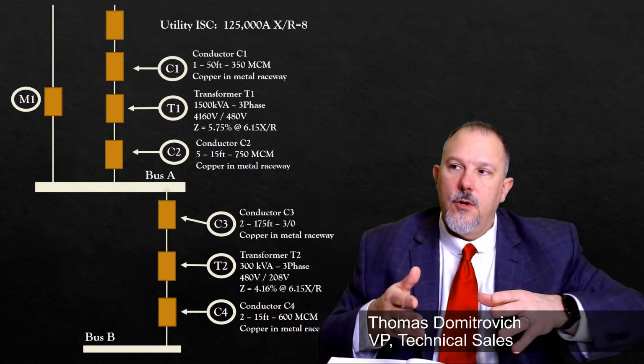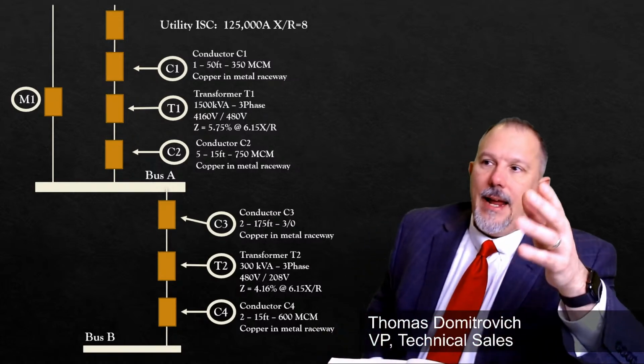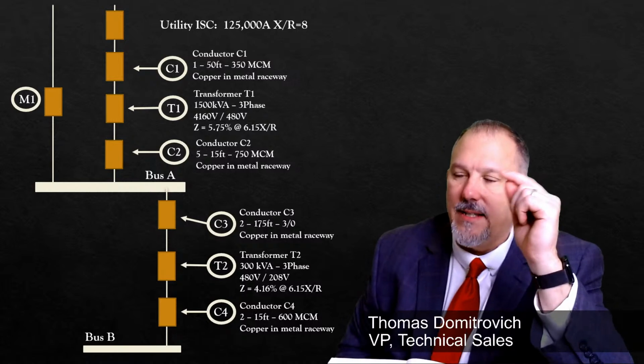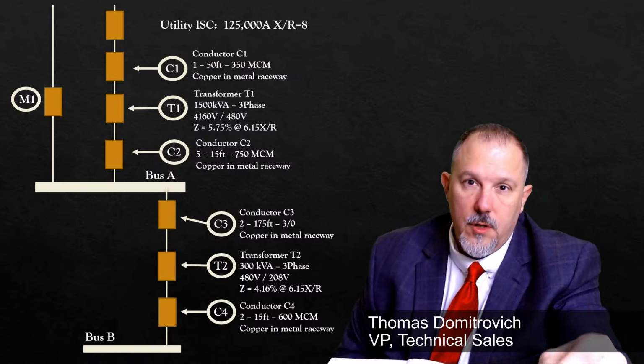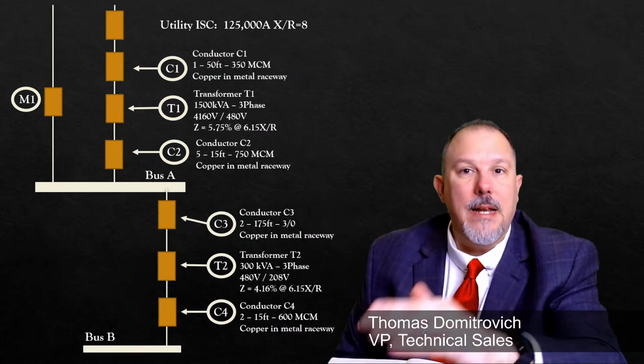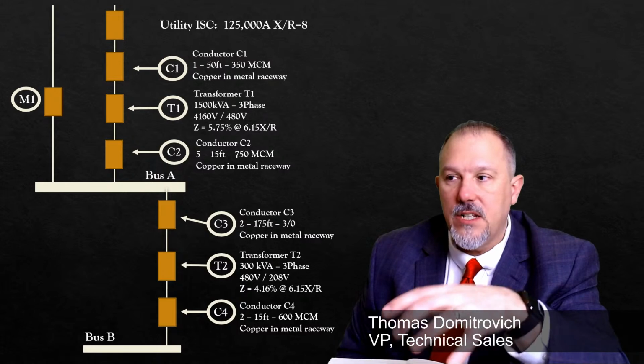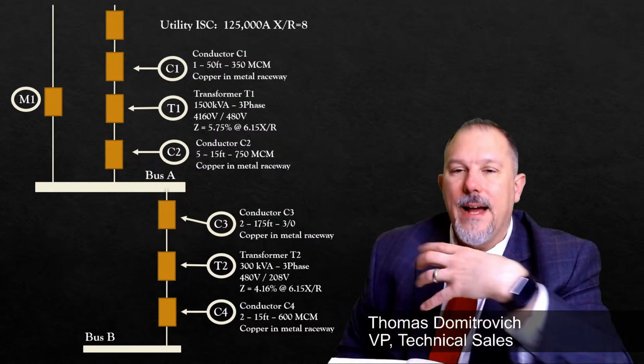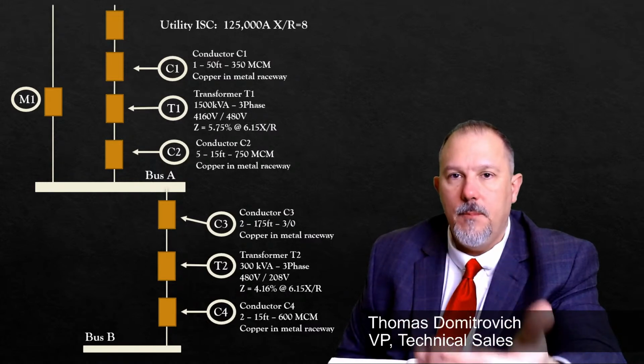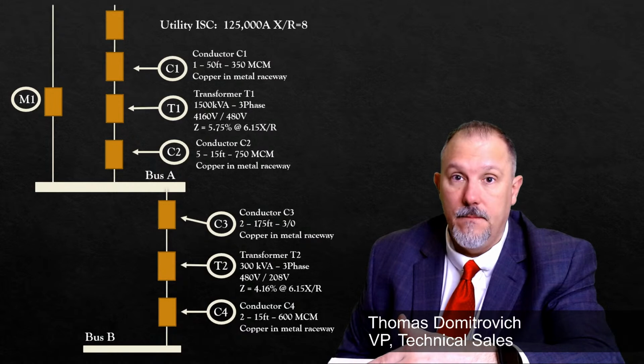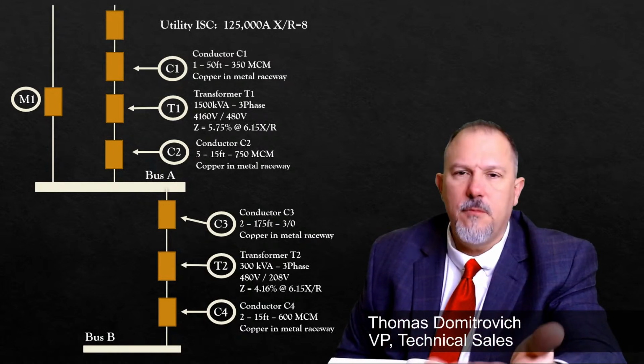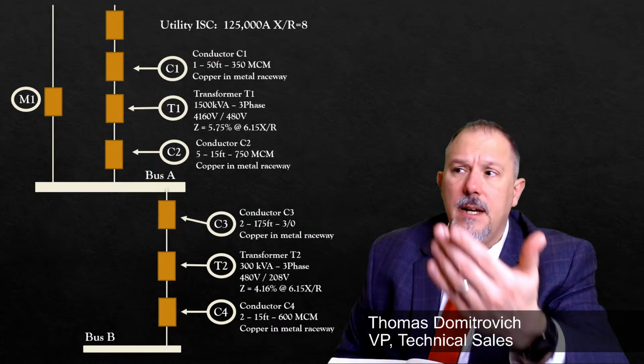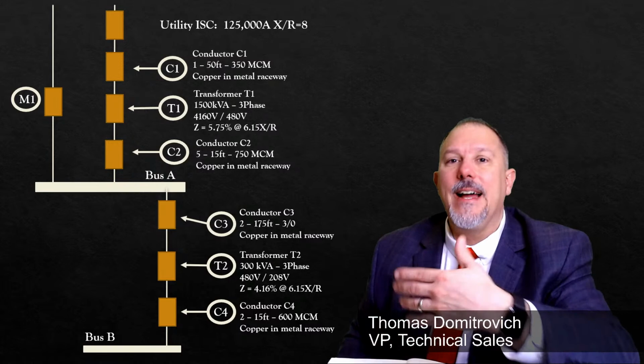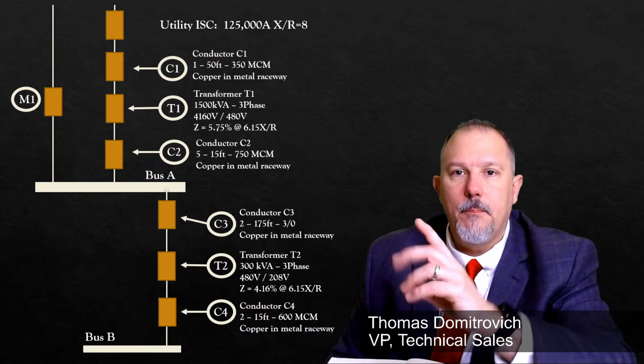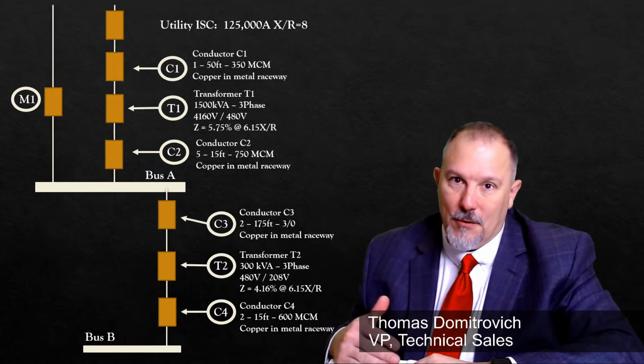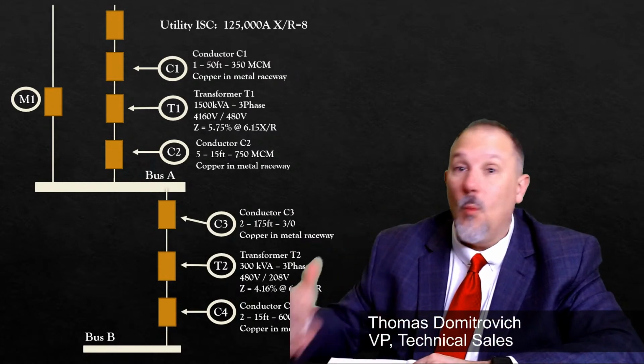Okay. So when you're modeling for interrupting ratings and short circuit current ratings, you're going to want to take the impedances of your transformers and multiply them by 0.9, minus 10%. Because based on IEEE standards, when I label a transformer with an impedance, it can be plus or minus 10%. If it's a single phase transformer, it's plus or minus 7.5%. But these transformers are going to be plus or minus 10%. So for the highest fault current, you're going to want to multiply the impedance by 0.9. For the low fault current, you're going to want to multiply it by 1.1.